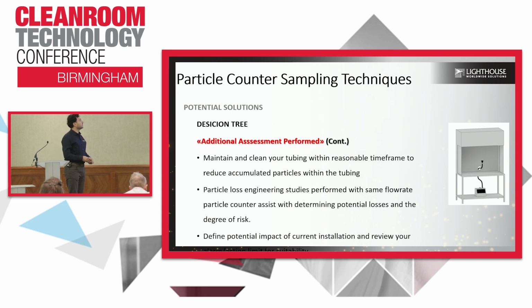Again, particle loss engineering studies performed with the same flow rate particle counter assist with determining particle losses and the degree of risk. So put the particle counter in the sample location. Count the same time period and see how you can correlate these two numbers. Are you able to capture the same risk conditions with the portable device as well as your system instrument? So if you can do it, then you are safe.